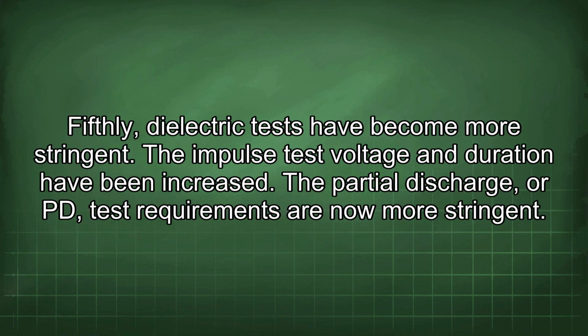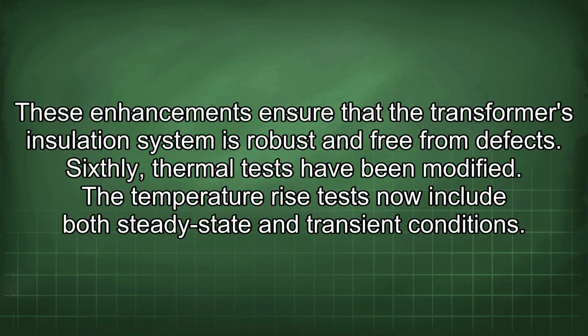Fifthly, dielectric tests have become more stringent. The impulse test voltage and duration have been increased. The partial discharge, or PD, test requirements are now more stringent. These enhancements ensure that the transformer's insulation system is robust and free from defects.